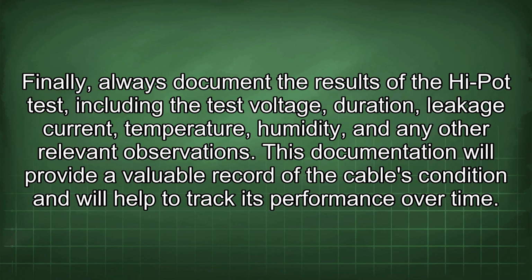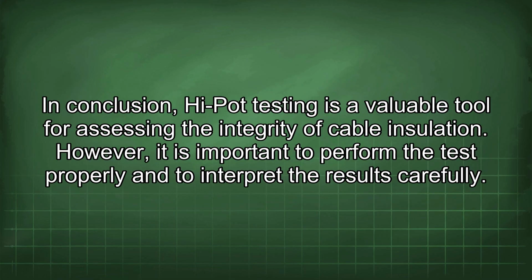Finally, always document the results of the high-pot test, including the test voltage, duration, leakage current, temperature, humidity, and any other relevant observations. This documentation will provide a valuable record of the cable's condition and will help to track its performance over time. In conclusion, high-pot testing is a valuable tool for assessing the integrity of cable insulation.